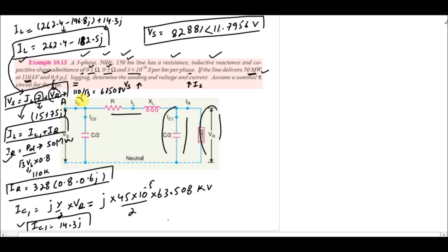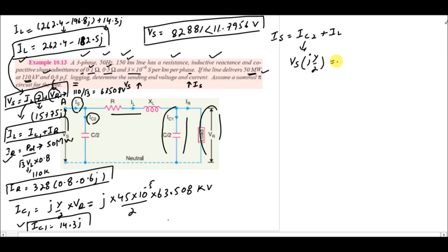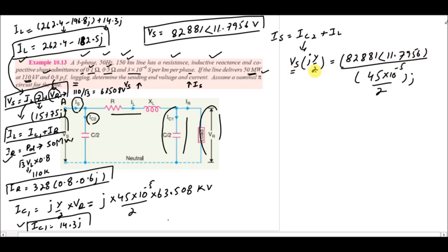To calculate the sending end current IS — the second part of the question — IS = IC2 + IL, where IC2 = VS × j(Y/2). Using VS = 82,881 ∠11.7956° V and j(Y/2) = j(45×10⁻⁵ / 2), we compute IC2.